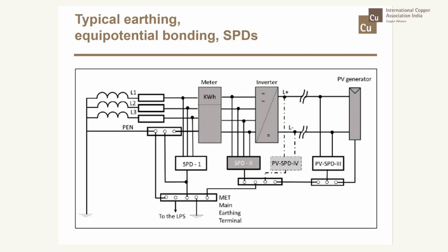You also need to have, if the distance is more than 10 meter, surge protection devices on both ends, that is on the array end as well as the inverter end. Similarly, from the inverter output, if the length is more than 10 meter, you need to provide surge protection on either side. The different classes of surge protections are shown.